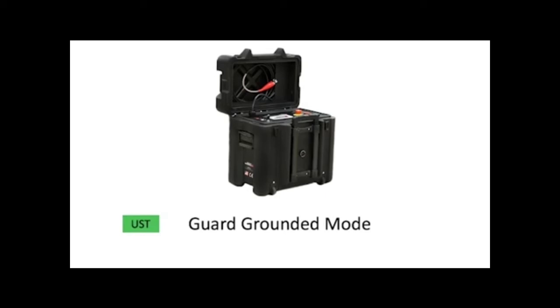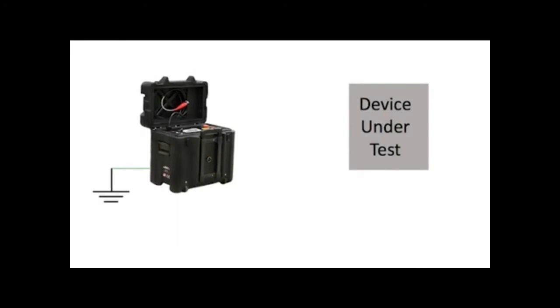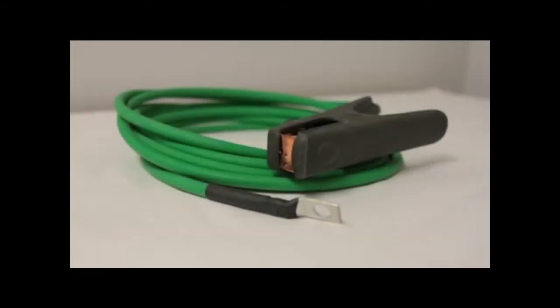This mode is used when very sensitive measurements are required. To begin testing in ungrounded mode, connect the DC HiPOT to the ground using the grounding cable.